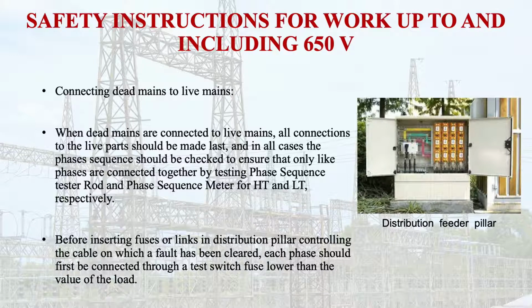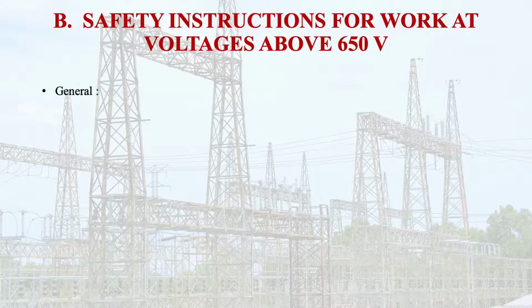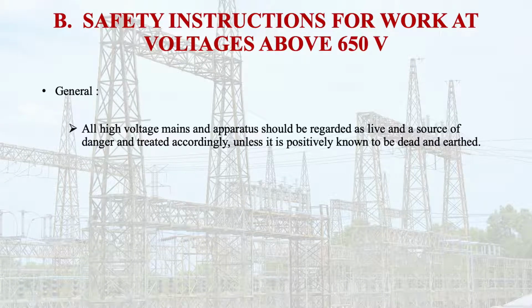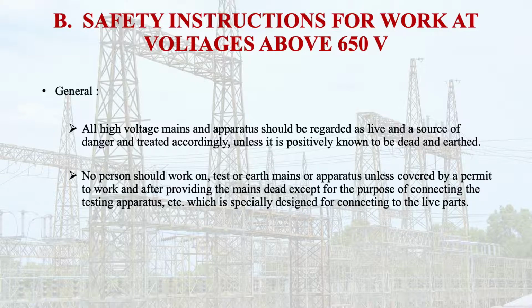So let us discuss the safety instructions for work at voltage above 650 volt. Some general instructions are: all high voltage mains and apparatus should be regarded as live and a source of danger, and treated accordingly, unless it is positively known to be dead and earthed. No person should work on, test or earth mains or apparatus unless covered by a permit to work, and after proving the mains dead, except for the purpose of connecting the testing apparatus, etc., which is especially designed for connecting to the live parts.